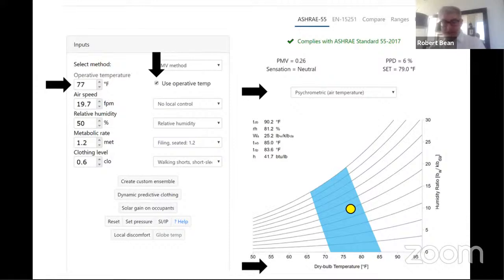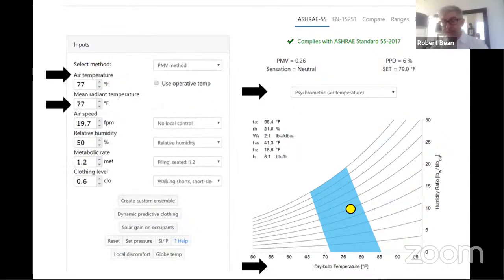And so we know that when we get the correct operative temperature in a space, we can then have a higher probability of being in compliance with the standard. And when we have a failure to control the operative temperature, which oftentimes has to do with poor architecture, poor fenestration systems, thermal bridging, all of these things will raise the operative temperature, which is 100% related to the MRT, or the mean radiant temperature. So we like to split these values apart. There are times when the MRT equals air temperature. Oftentimes that will be in the interior of spaces, spaces that are not at the top floor, not towards the exterior, not exposed to the solar loads that we typically find.